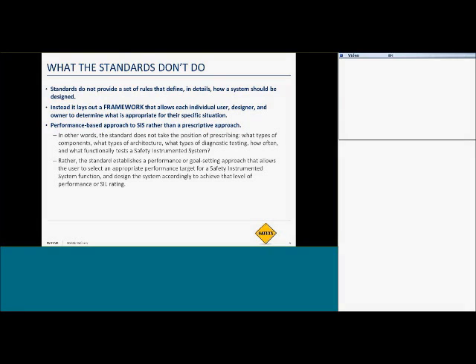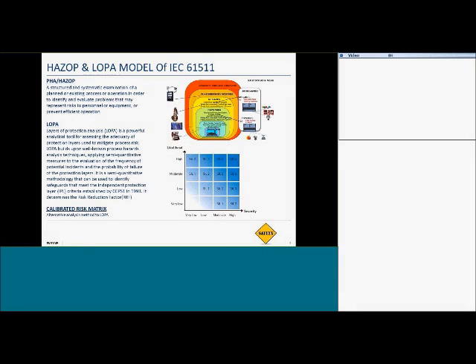So that's why you might see one customer for this piece of equipment, say a heat exchanger, calling the valves around their heat exchanger SIL 1, and meanwhile the very next customer is doing the same application and they want SIL 2. And we'll get into those SIL levels and how those are applied. And we're going to talk a little bit about this framework itself and how it applies to customers and different strategies that they might utilize, and why we might be seeing different SIL levels for the same application. So first we'll get into understanding some of the terminology and some of the processes around 61511.